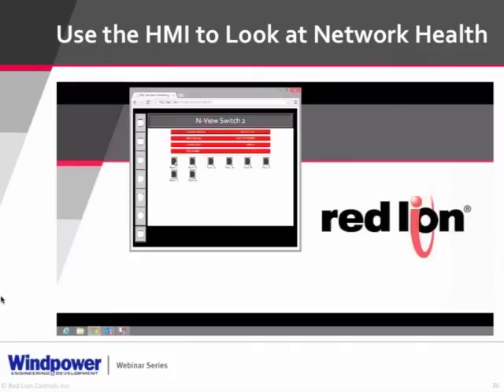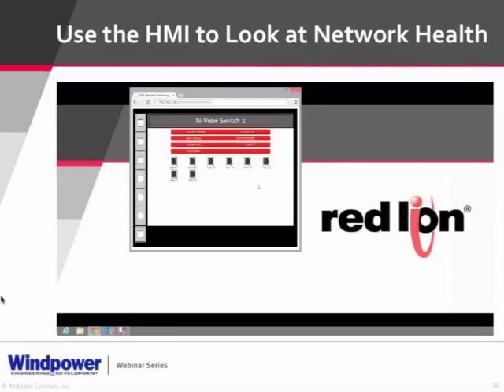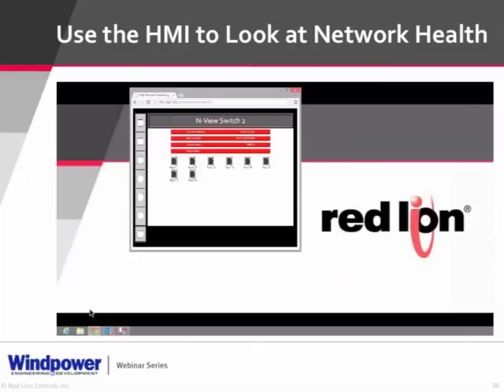We also have the DSP, which runs the same Crimson software and is configured identically to the G3 but without a touchscreen. A key benefit for retrofits: you may end up with PLCs from different manufacturers using different protocols. The DSP performs protocol conversion — talking from one protocol language to another — so you can phase your retrofit instead of replacing everything at once. The HMI lets you walk to the base of the tower, pull up network statistics from the G3, and get full network visibility without being a network administrator and without climbing the tower.